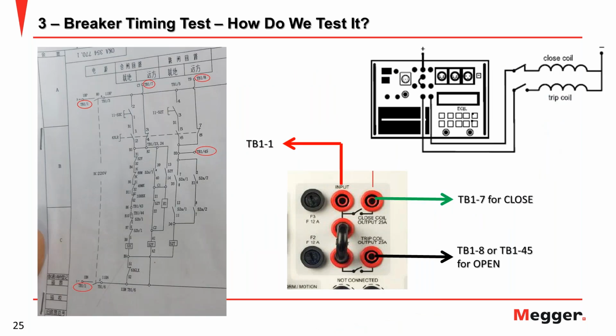This is an example of how we connect to the coil. This is an example of the single line diagram of the circuit breaker. To the control circuit, we need to connect at least three terminals, and some equipment needs four terminals. You need to find the positive terminal, negative terminal, and the close and open coil terminals. So like this, you can see this is the closing coil, and this is the tripping coil.